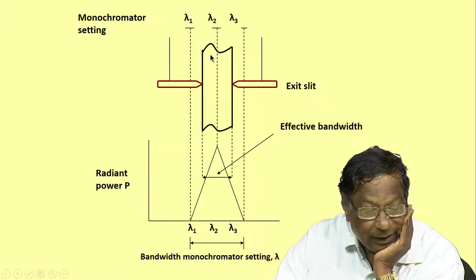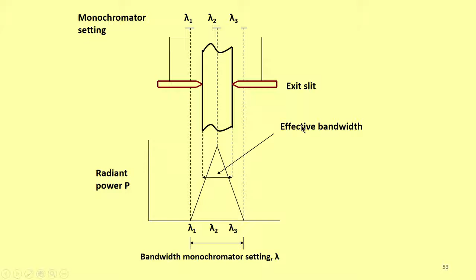I have the monochromator radiation, and then I have a slit here. According to this slit, I am getting electromagnetic radiation of wavelengths lambda 1, lambda 2, lambda 3 like that, but the maximum intensity of the radiation is at lambda 2. A small portion of lambda 1 is collected, and a small portion of lambda 3 is also collected. It is the endeavor of every instrument manufacturer to reduce this lambda 1 and lambda 3, because we want to choose only lambda 2. So, this is known as the bandwidth of the monochromator setting, and the width at 50% of the intensity is known as the effective bandwidth. Okay. So, this is the radiant power.